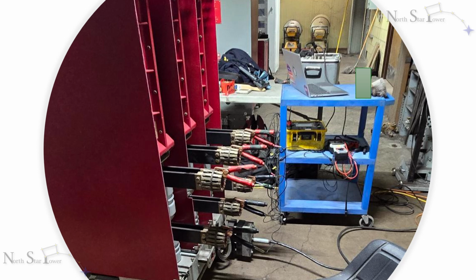In timing tests, we measure how quickly the breaker opens and closes, down to the millisecond. Timing matters. A breaker that hesitates even a few seconds can allow a fault to escalate, causing major damage. We also check that each phase opens and closes in sync. Uneven timing can be related to internal strain or improper contact sequencing.